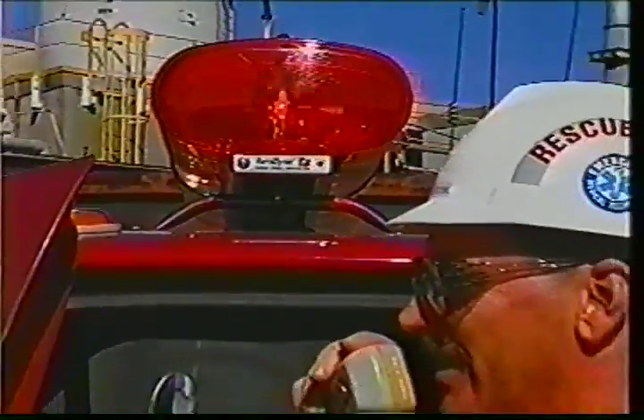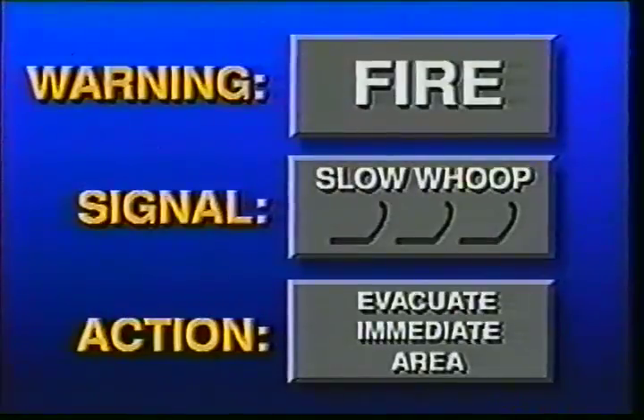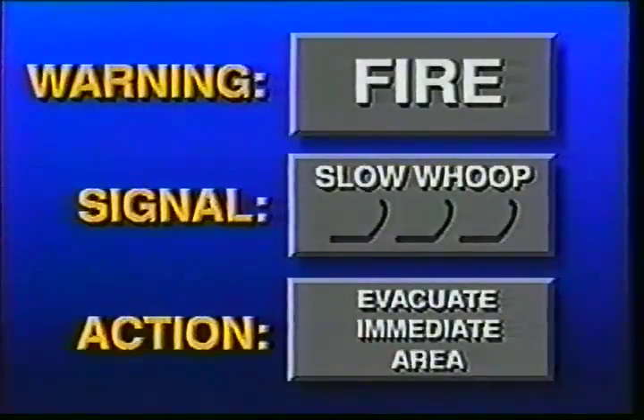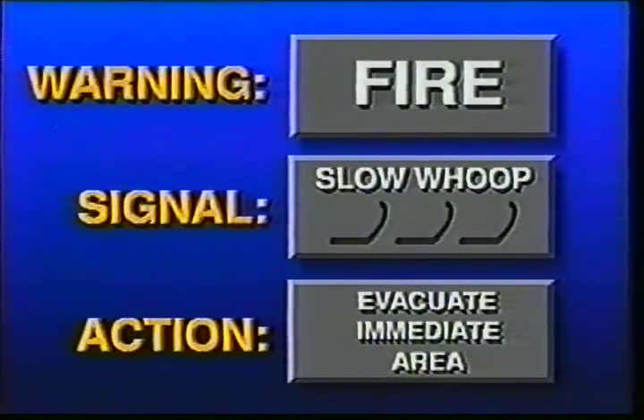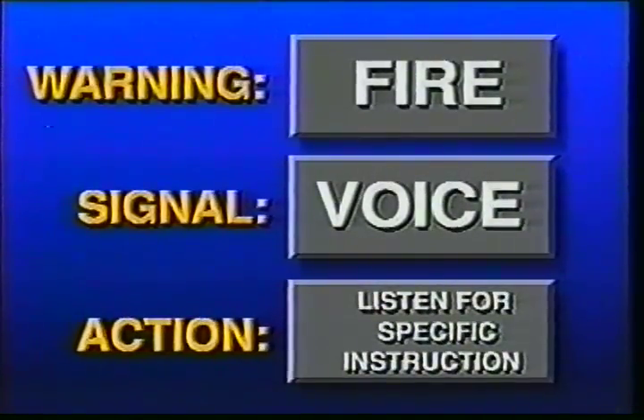Another alarm that may require your attention is the fire alarm. This alarm involves a slow whoop, which may be followed by voice instructions. If you are in the immediate vicinity of a fire, you will only hear the slow whoop sound, and you must evacuate away from the fire area. If you are in another area of the plant, you would hear the alarm and then a voice message describing the location of the fire, plus any instructions specific to the area where you are located. In some areas, you may have to move closer to the speaker to clearly hear the voice instructions.